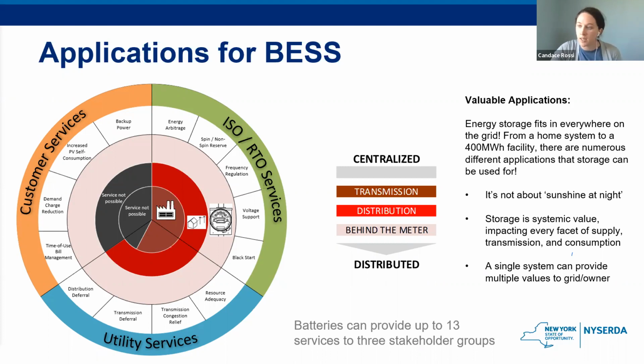And then lastly, you have what's considered the black start. In the event of a grid outage, black start generation assets are needed to restore operation to large power stations in order to bring the regional grid back online. So most of these transmission level applications are just to ensure that our grid is being used stably and properly. It just gives that extra level of resiliency.